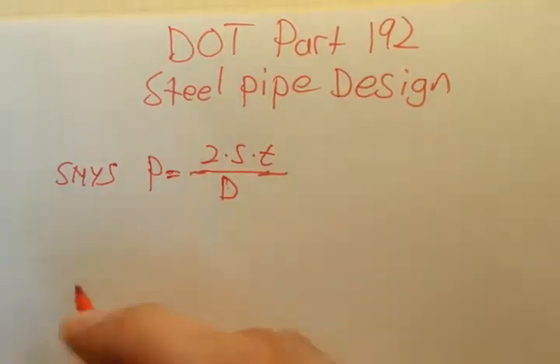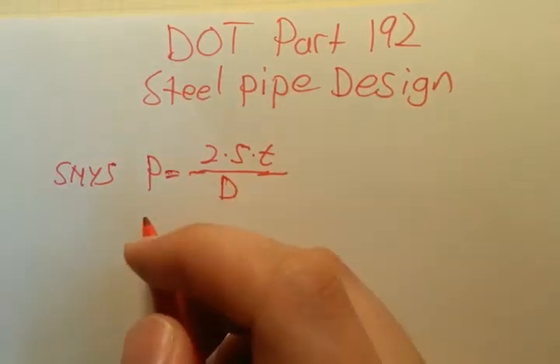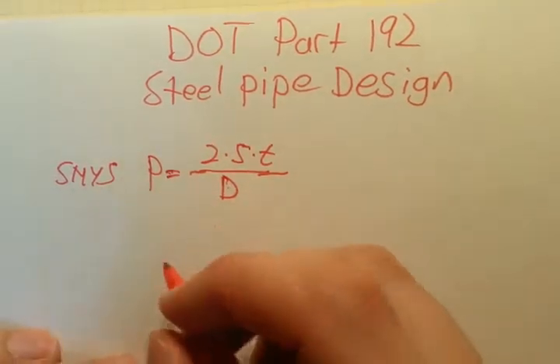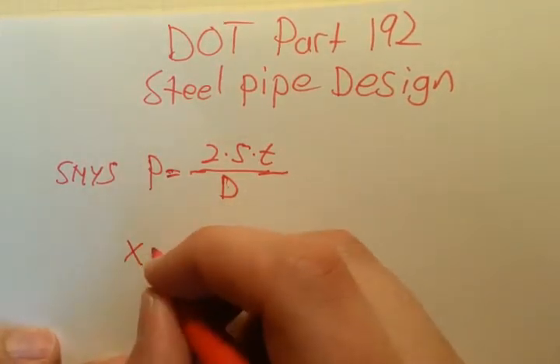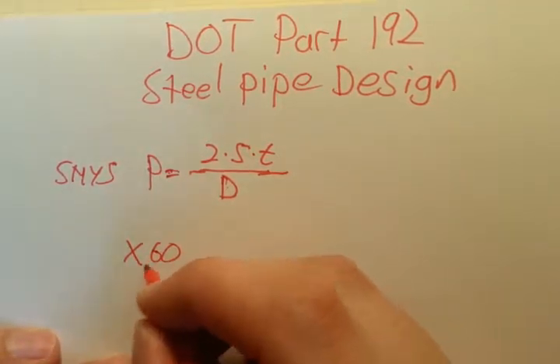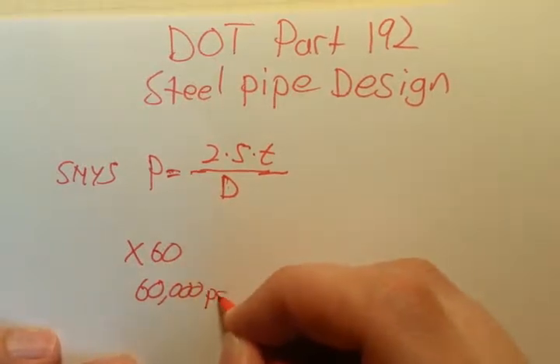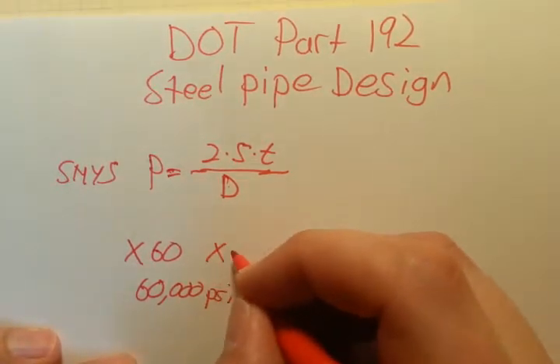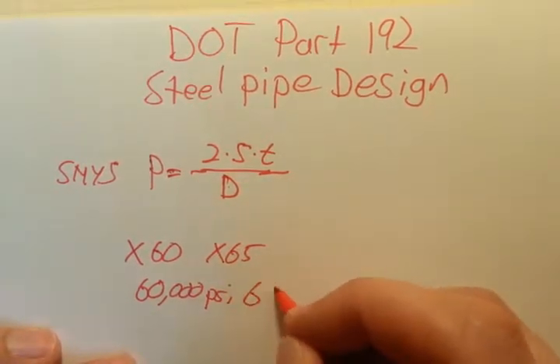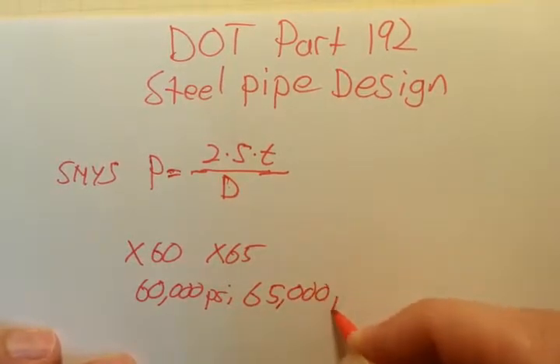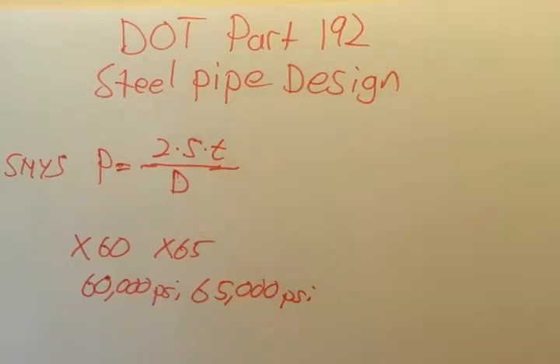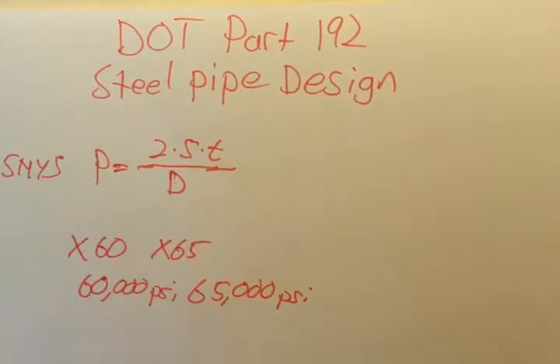I'll run through these really quick. S, the yield strength, is typically denoted in the industry as X and then a number. So X60 would be 60,000 PSI, X65 would be 65,000 PSI, and so on. You can actually get custom yield strengths made; they don't have to be in multiples of 10 or 5.